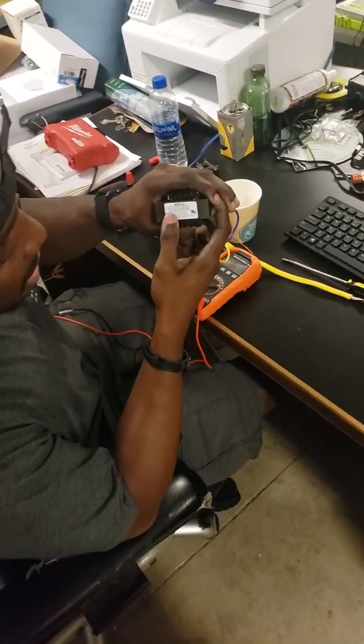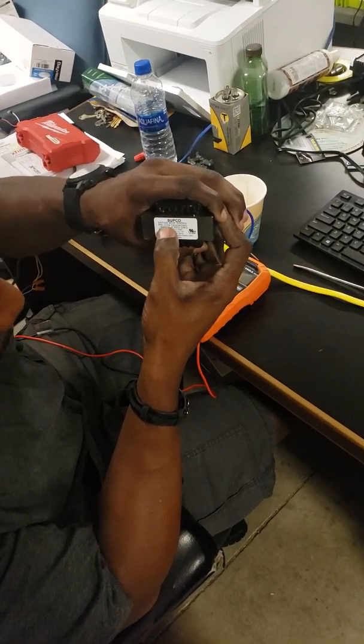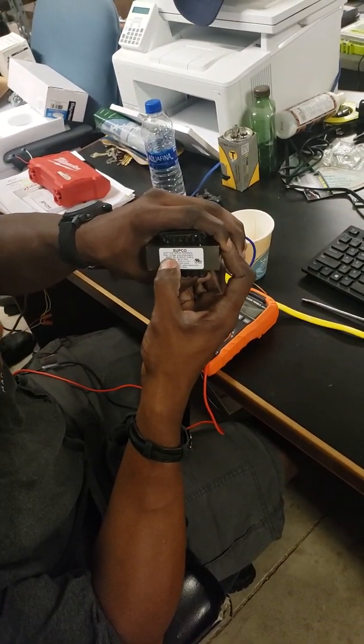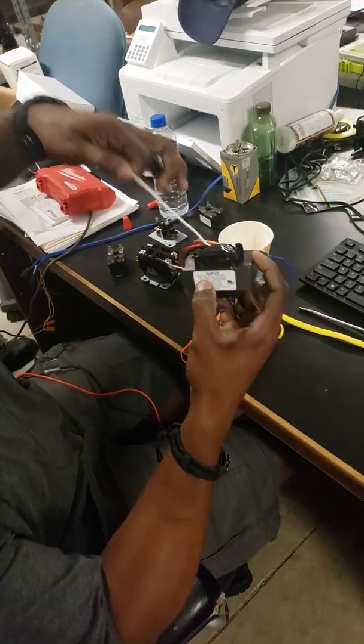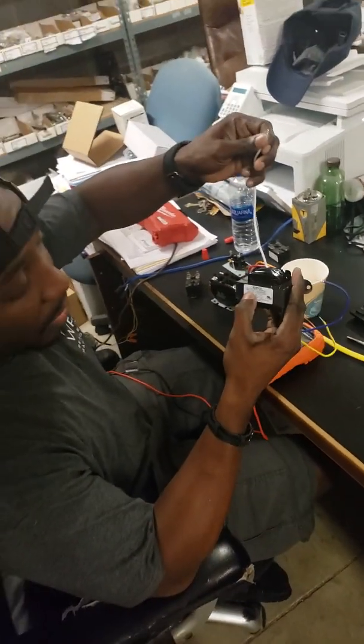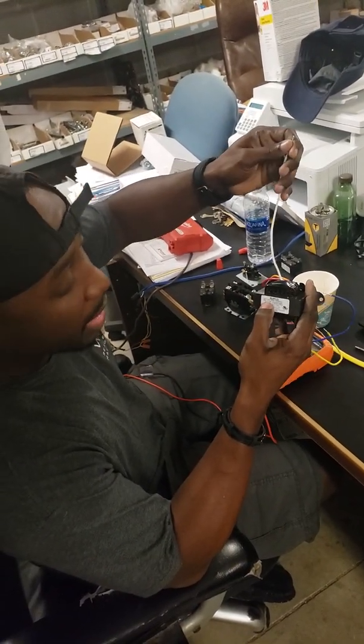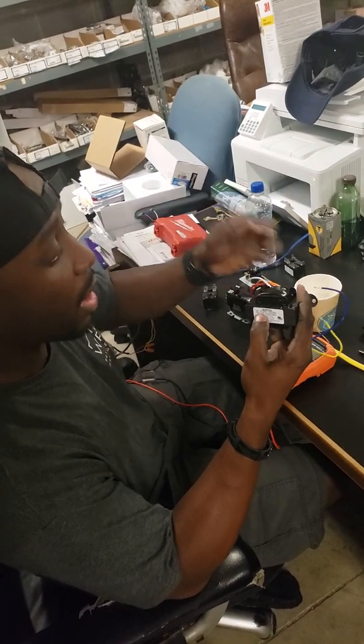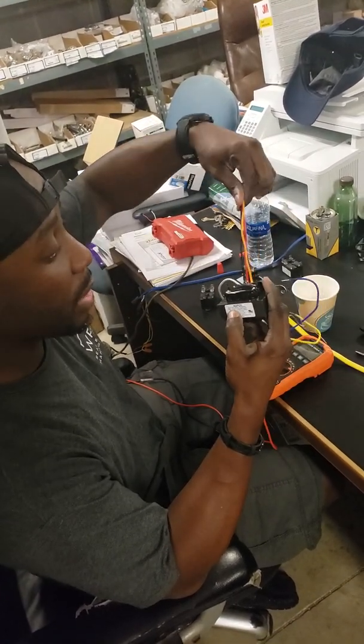In this particular instance, the common wire is, if you look right underneath of it, the white wire. So the white wire has to be hooked up no matter what. You always got to have your white wire hooked up since it's the common wire. It's going to be the commonality between all the rest of these three wires and what they do.